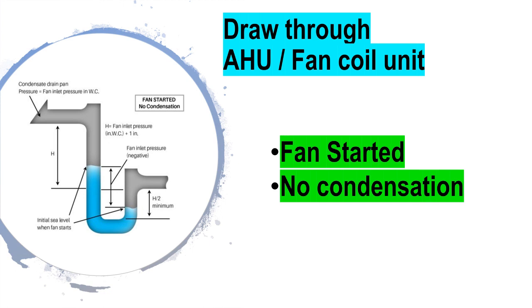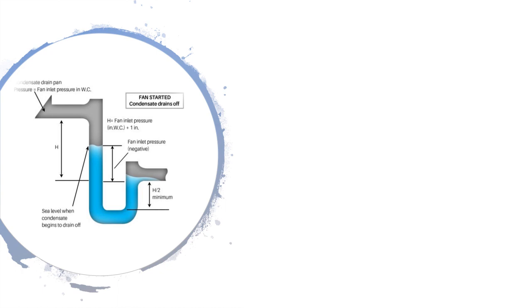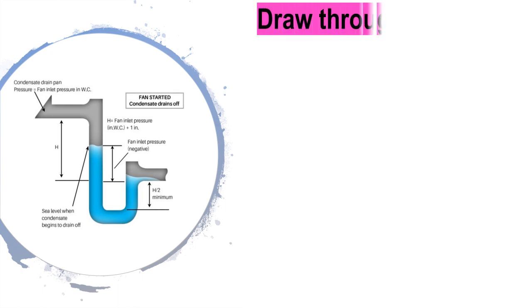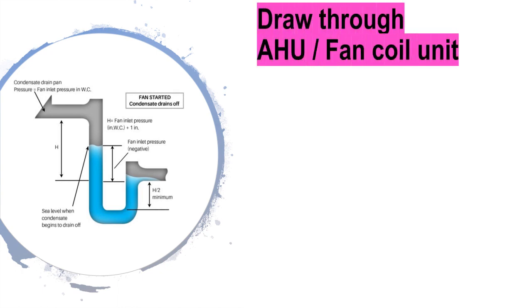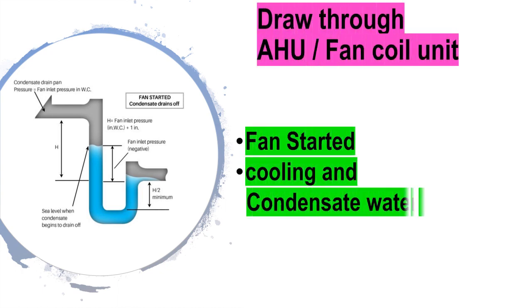When the fan starts and condensation has not yet begun, the water level of the U-trap increases on one side due to fan static pressure. That rise is J, which equals H divided by two. Now, as cooling and condensation begin, water starts to drain off.